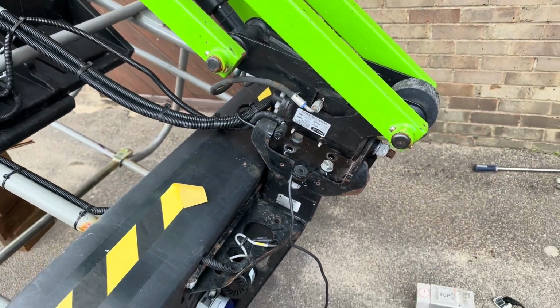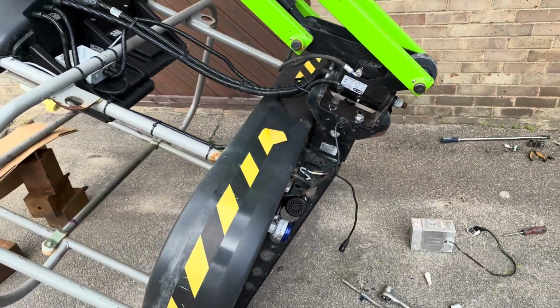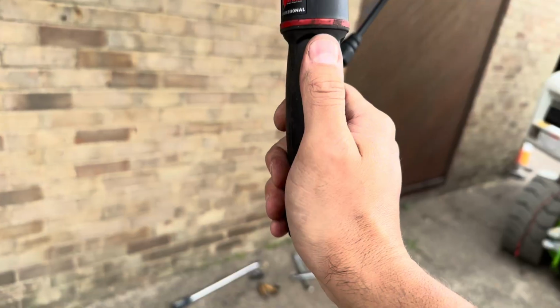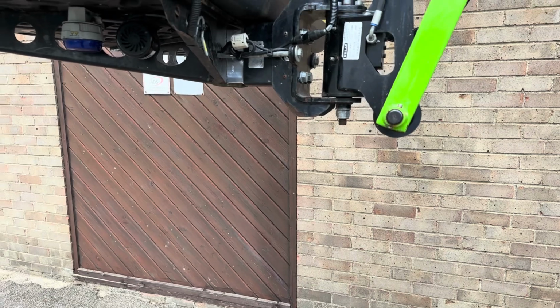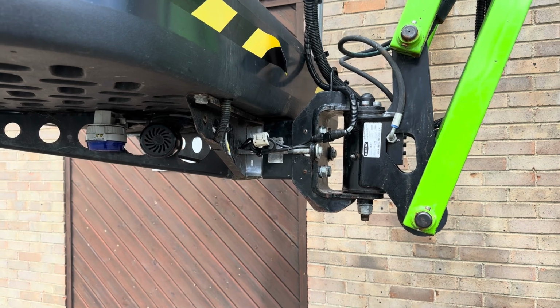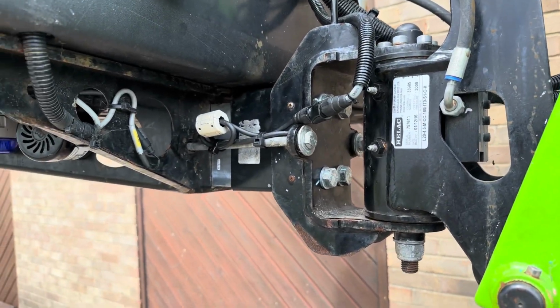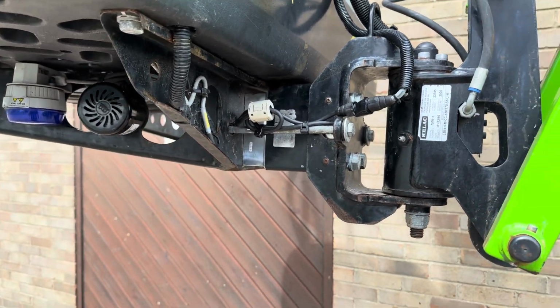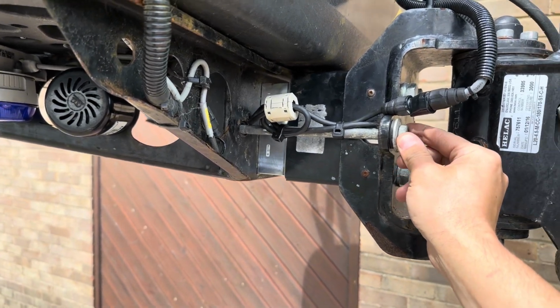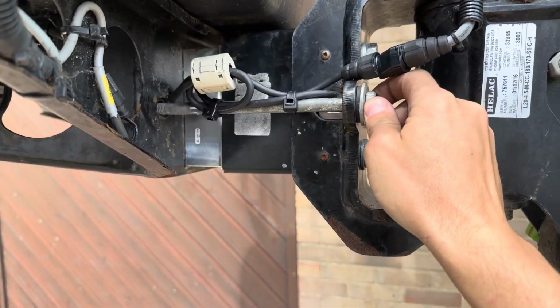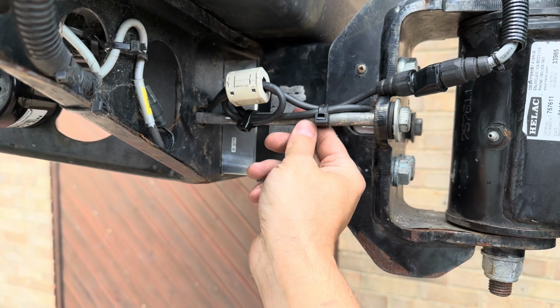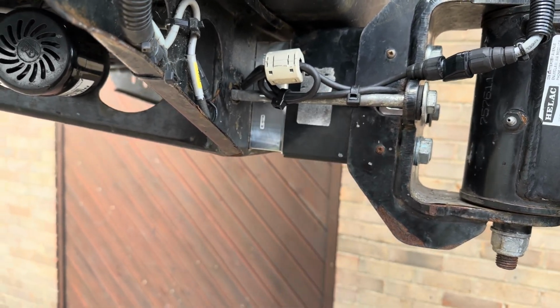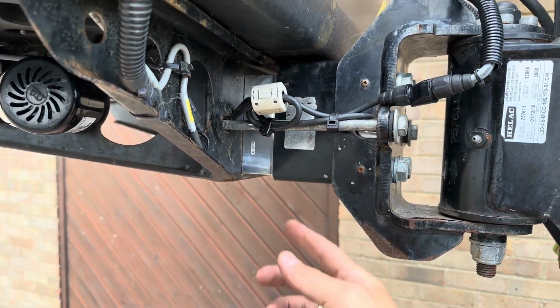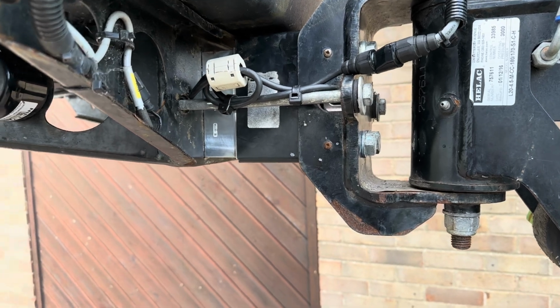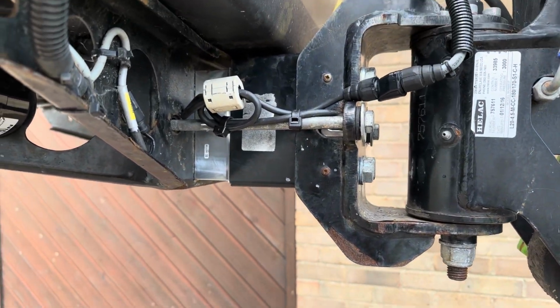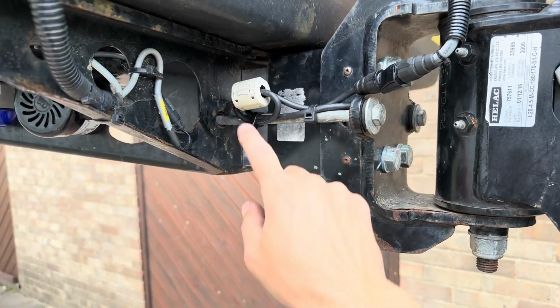Okay, so that's where we are. I'm going to lift this off now and finish it. So here it is, the new cell is in. All bolts are back in. Never make those bolts too tight. They should have a bit of play, 2-3 mils. If you make them too tight, you will have trouble with the calibration. Okay, so that's done. Cable's connected, the filter is back on.